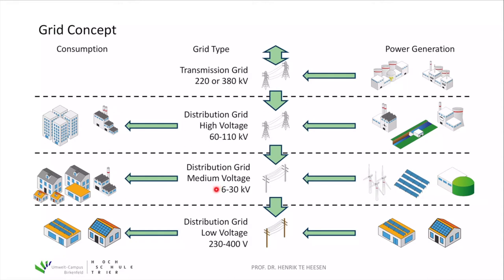The third level is the medium voltage distribution grid with a voltage of 6 to 30 kilovolts. On the power generation side we have typically wind turbines, PV systems, or bioenergy systems feeding into the medium voltage grid. Large renewable energy systems like offshore wind parks can also feed into the high voltage grid, while mid-sized wind energy parks feed into the medium voltage grid. Consumers at this level include villages and small to mid-sized companies.